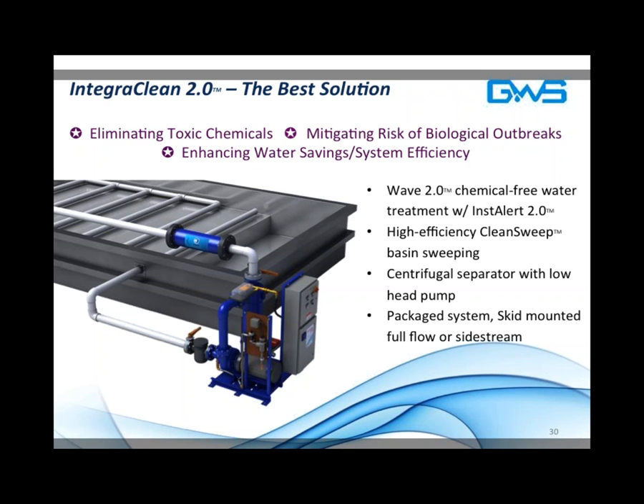And it's my opinion as a filter company president here that all cooling towers should have effective solids management, because solids management is part and parcel of mitigating the risk for Legionella. And that's a significant concern. So managing the solids within cooling tower systems is essential for Legionella control and biological management. Wave will do an excellent job on top of that, or instead of that, for managing biological control.